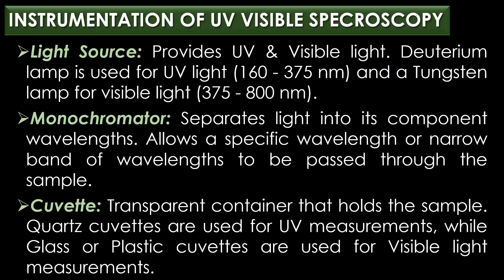First, the light source provides UV and visible light. Commonly, a deuterium lamp is used for UV light ranging from 160 nm to 375 nm, and a tungsten lamp is used for visible light ranging from 375 nm to 800 nm. Second, the monochromator separates the light into its component wavelengths and allows a specific wavelength or narrow band of wavelengths to be passed through the sample.